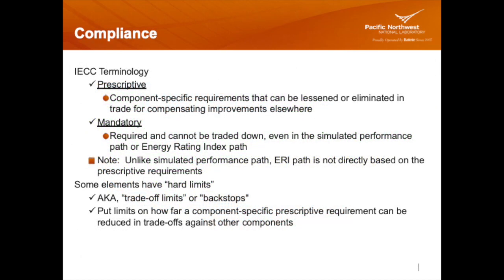Prescriptive components of the code are component specific, so a specific R value of insulation, a specific U value, a specific piece of equipment has to have a specific efficiency rating. That's the prescriptive part of the code. So if you're following a prescriptive path, or a mandatory path that has a prescriptive note to it. Mandatory requirements are required and cannot be traded down. If you're looking at lighting, for example, some of the paths allow you to trade off lighting in one space so you can increase lighting power density in another. That's an example of a tradable thing.